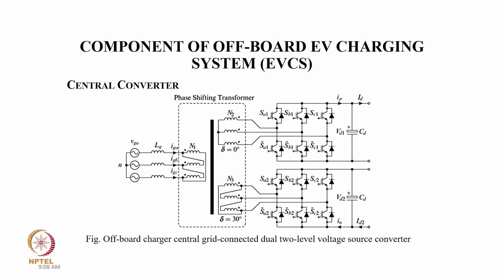Now here you can see a phase shifting transformer that provides a concept equivalent to 12 pulse. This is an off-board charger with a central grid connected two-level voltage source converter. What is interesting here is that we typically have a phase shift of 30 degrees between the two converters, and these two converters are feeding the DC to separate buses. So you are able to reduce the harmonics on the grid side both by increasing the equivalent to 12 pulse, and by the low frequency operation you can easily have a sinusoidal current on the grid, and you can have bidirectional power flow for the central inverter.